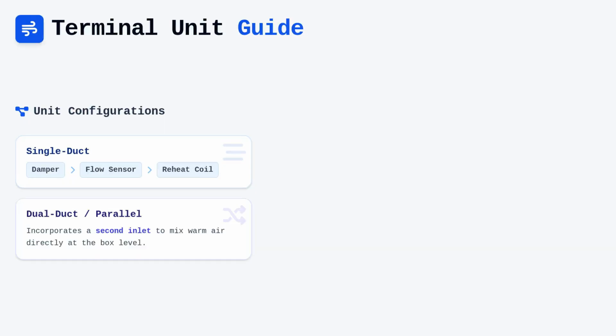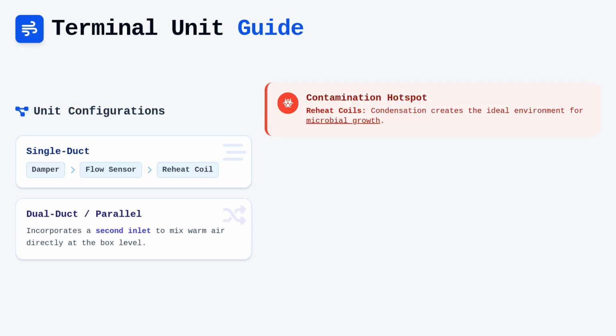The internal configurations of these terminal units vary, ranging from simple single-duct assemblies to more complex dual-duct or parallel fan-powered boxes. A single-duct unit generally consists of a damper, a flow sensor, and potentially a reheat coil, whereas dual-duct systems introduce a second inlet for warm air to be mixed at the box level. From a contamination standpoint, the reheat section is often the most problematic area because moisture condensation on the coil surface can foster microbial growth over time.